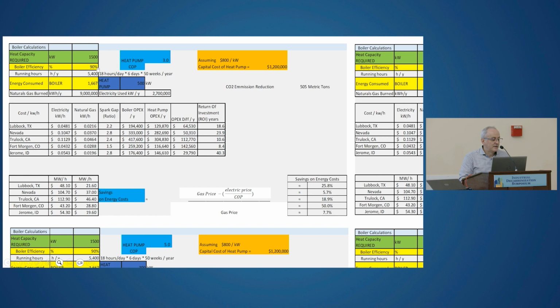If you look at efficiency, say you need 1,500 kilowatts of heating capacity and you have a 90% efficiency boiler, running 18 hours a day, 6 days a week, 50 weeks in the year, that's a total of 5,400 hours per year. At that efficiency, to make 1,500 kilowatts you need to consume about 1,600 kilowatts on the boiler. That's a total of 9 million kilowatt-hours per year.